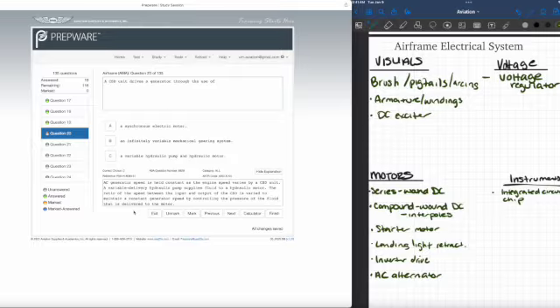AC generator speed is held constant as the engine speed varies by a CSD unit. A variable delivery hydraulic pump supplies fluid to the hydraulic motor. The ratio of the speed between the input and output of the CSD is varied to maintain a constant generator speed by controlling the pressure of the fluid that is delivered to the motor.